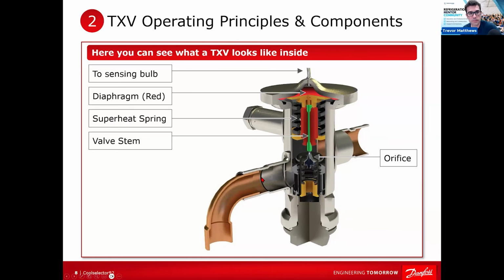Okay. But the trick is you've got to heat the pipe up before the valve, because the only part of the valve you're heating up is just that end. So point the heat away from the valve, heat the pipe up first. It'll heat up in a few seconds. Once it starts to turn cherry, back it up, put your Silfos on, away you go. Do not use flux, because the chloride in the flux will actually make pinholes in the valve.